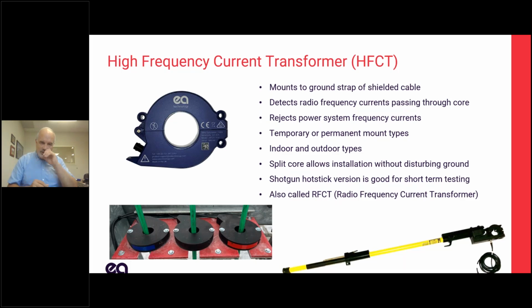So this high frequency current transformer, there's a variety of different things. They're also called RFCTs, or radio frequency current transformers. It mounts on the ground strap of the shielded cable. We don't want to mount on a conductor for safety reasons and also for saturation reasons. If I've got 500 amps going through a cable and I'm trying to pick up 500 microamps on a transformer going through the same bore of the transformer, that's kind of hard. There should be very little current flowing through the ground strap so I can be more sensitive.